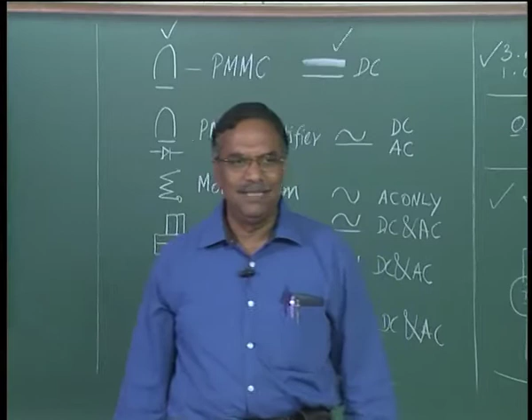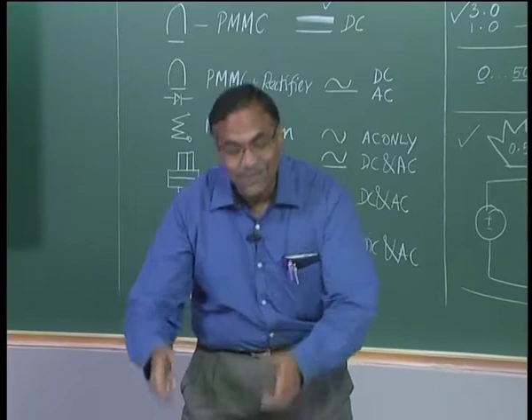For example, we talked about taut band suspension. Taut band suspension type meters are very sensitive to vibration. If I take the meter and place it carelessly, the taut band suspension will get damaged. So you have to read the instructions, and even when placing the meter, place it very slowly, do not hit the meter hard.